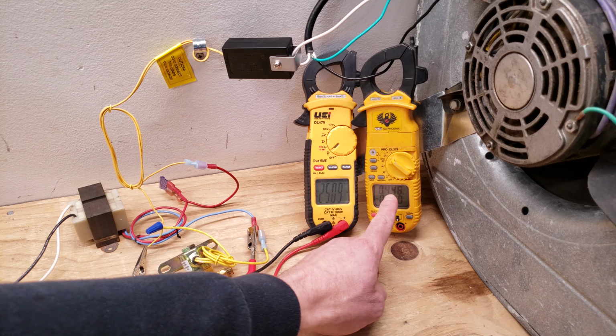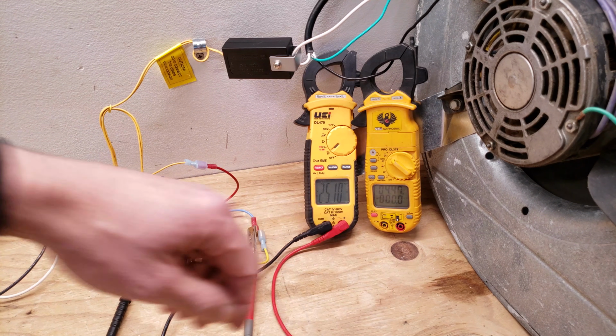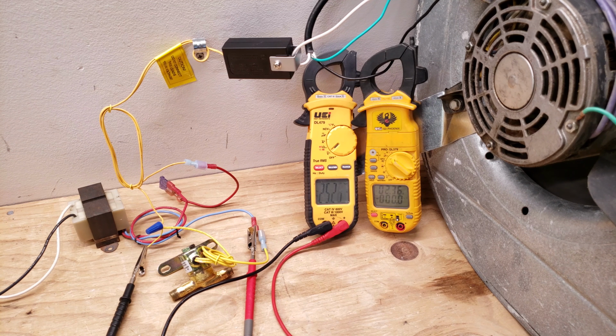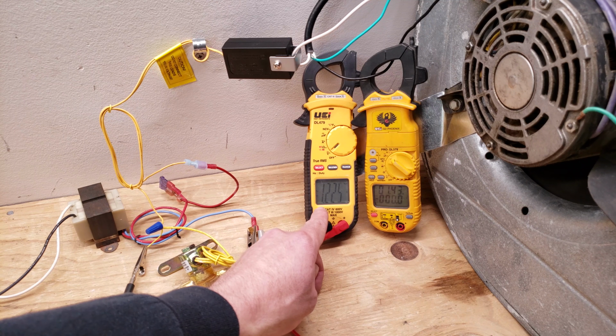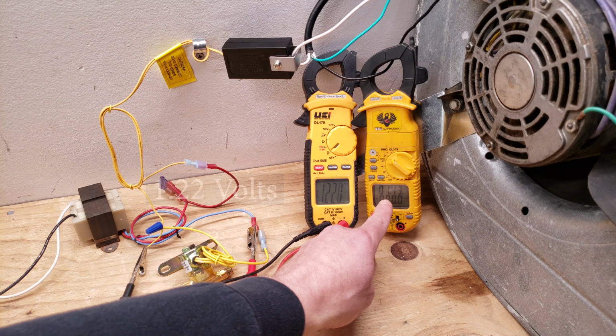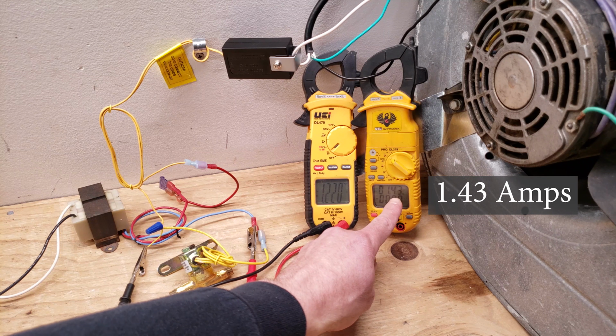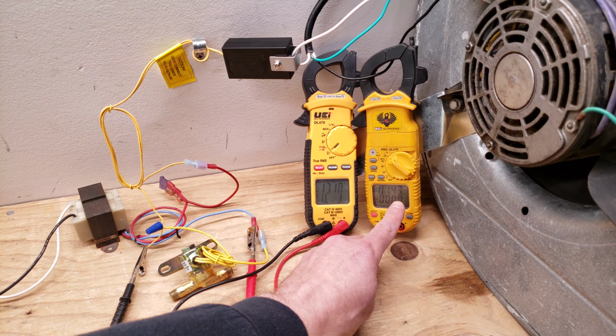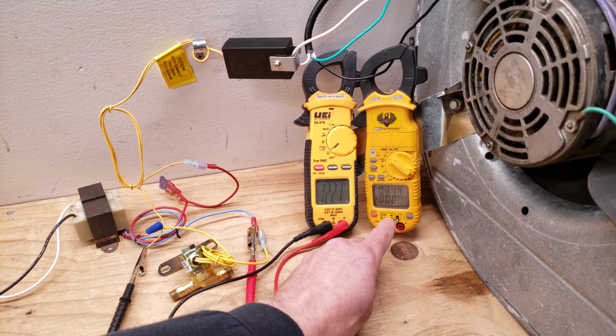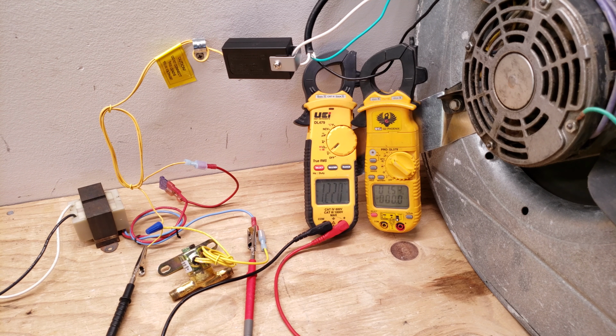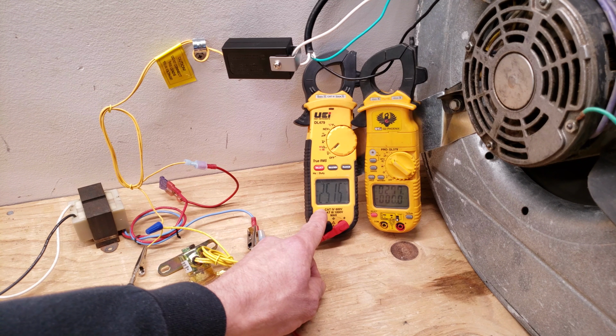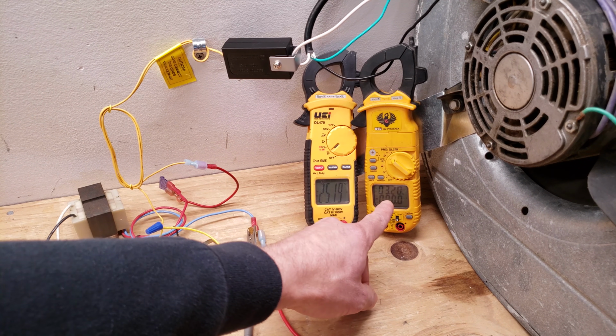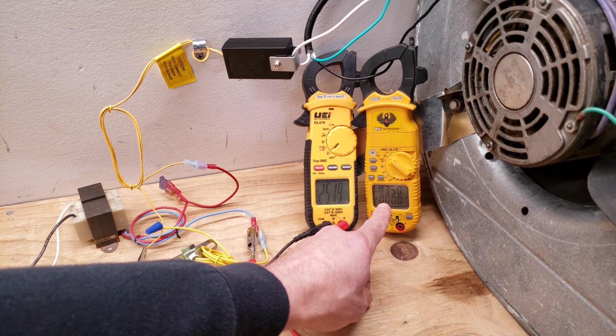Now what I'm going to do is lower the amperage by closing off the air pathway. So you see that now it reads 1.22 amps, and we're only drawing 1.43 amps. Now I'm going to slowly increase the amount of airflow coming from the blower motor, and that's going to increase our amperage. And you see that now we're allowing the 24 volts to the solenoid again, and we were drawing right about 2.3 amps when that happened.